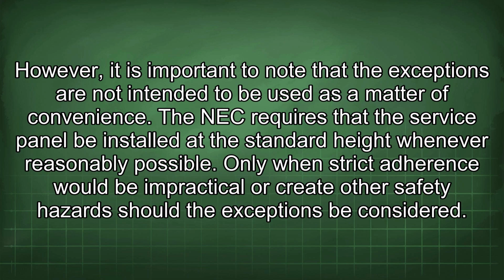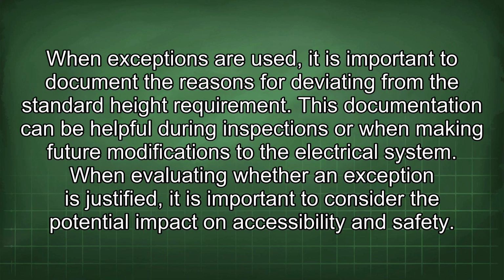The NEC requires that the service panel be installed at the standard height whenever reasonably possible. Only when strict adherence would be impractical or create other safety hazards should the exceptions be considered. When exceptions are used, it is important to document the reasons for deviating from the standard height requirement. This documentation can be helpful during inspections or when making future modifications to the electrical system.